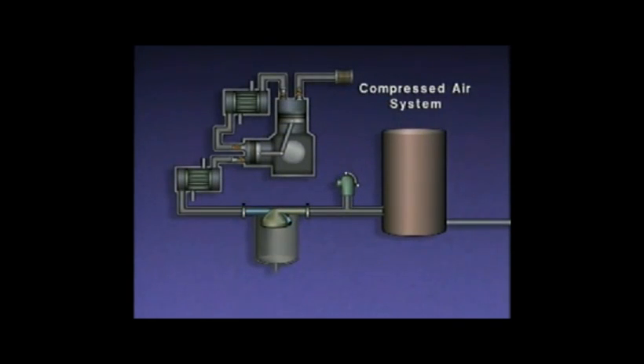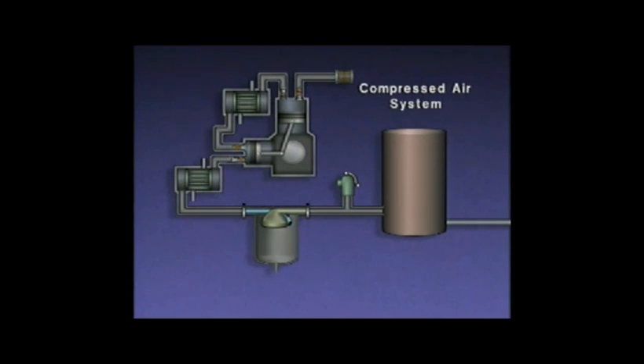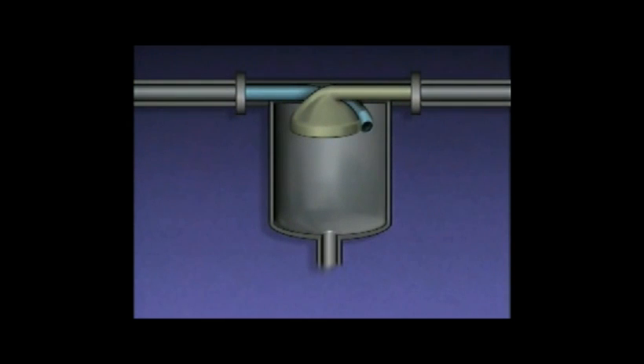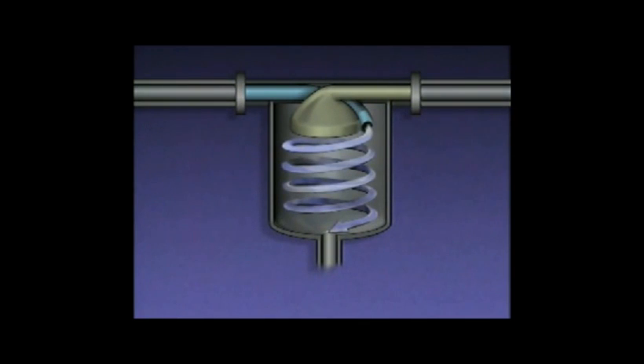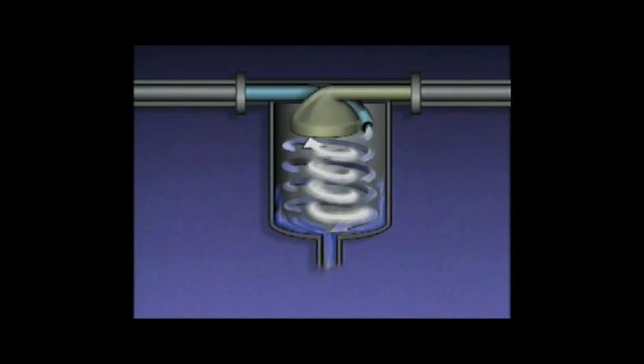During the cooling process, any water vapor in the air condenses, so there may be moisture in the compressed air. The compressed air is sent from the aftercooler to the demister, which removes moisture to prevent it from damaging equipment. Inside the demister, the compressed air is swirled around inside a cylinder. The swirling action causes the heavier moisture to separate from the lighter air and collect in the bottom of the cylinder, where it is drained from the system. The dry compressed air is then routed to other components.